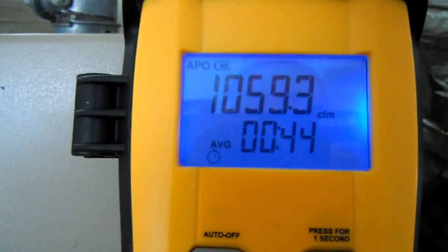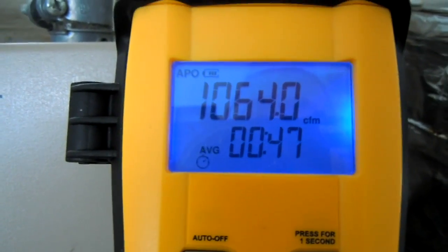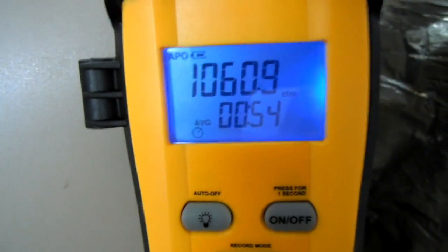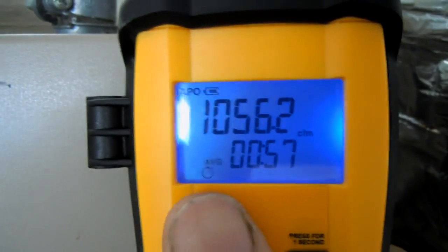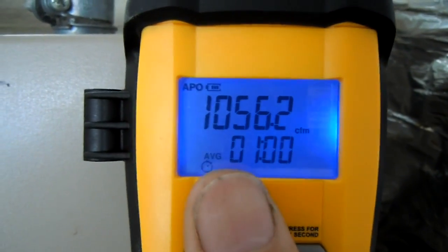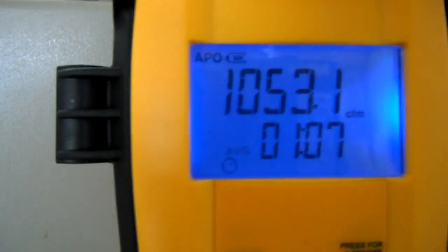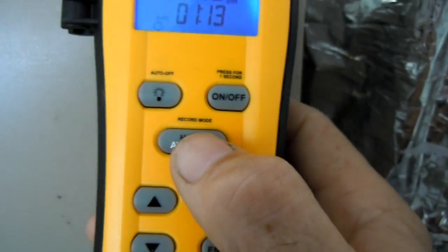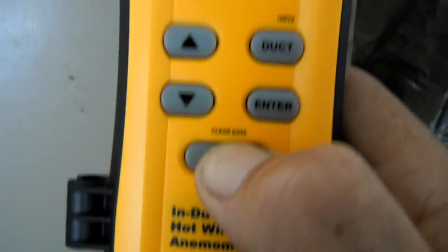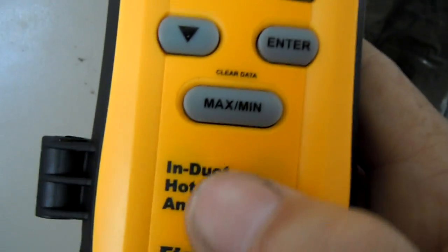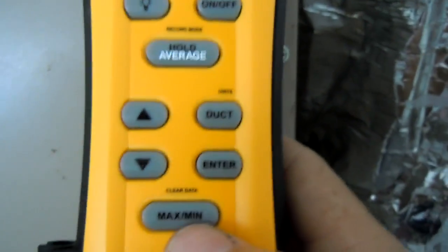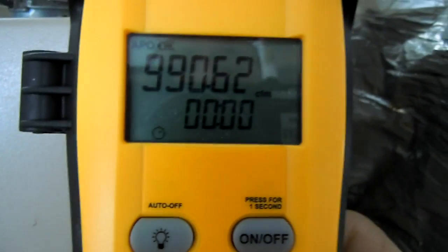It's really a great way to check a lot of different things like your ducts for leaks. My supply has one thousand, we'll just say one thousand sixty because trying to get it exact as you can see is just not going to happen. We'll turn off the averaging and then reset the clock by pressing and holding this maximum minimum button down here. You see that resets the clock.